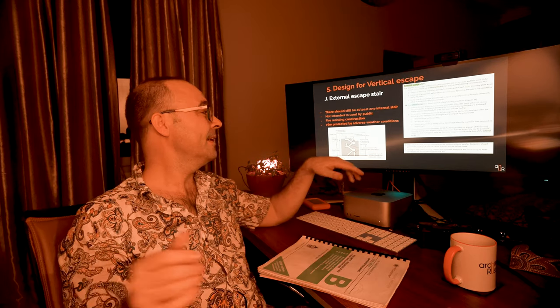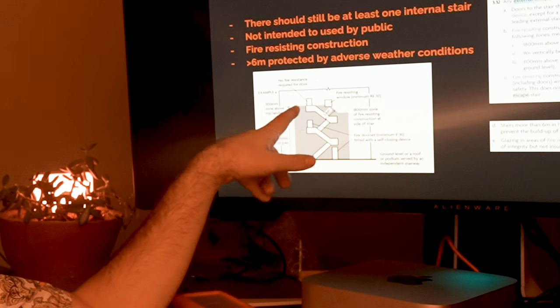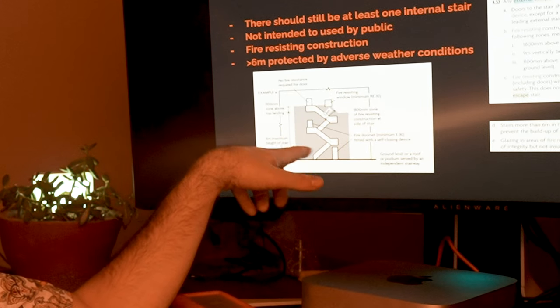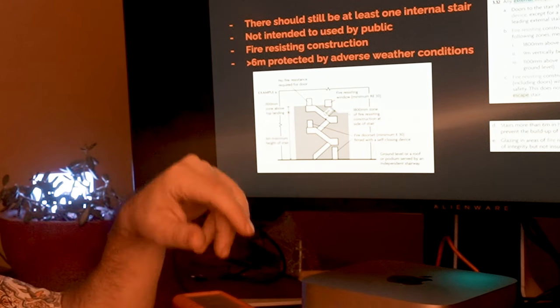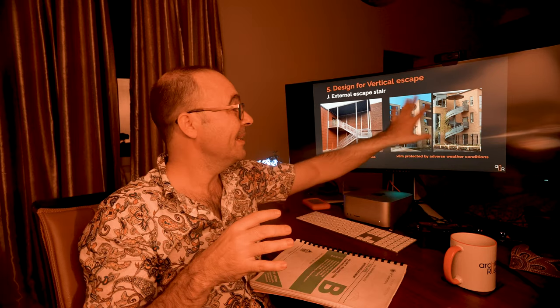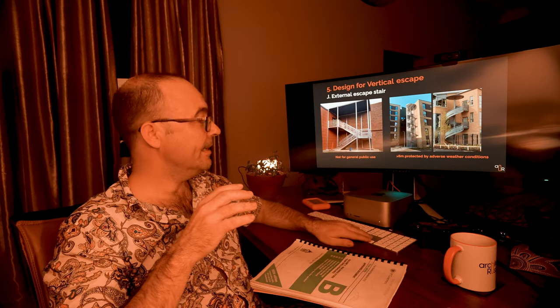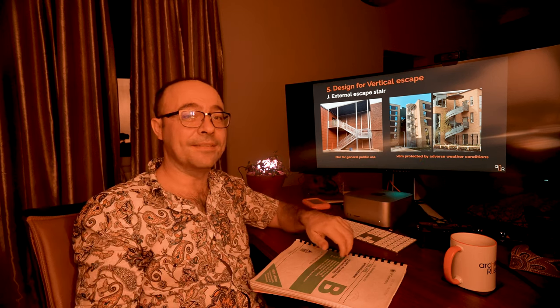There are external escape stairs as well. Usually you need to have at least one internal escape stair if you have an external escape stair open. There are also areas around the escape stair that need to be protected — you're not allowed to have windows within certain distances, as shown in this document. It's got to be protected from adverse weather conditions, and these external stairs are not for public use — they're only used in the event of a fire.